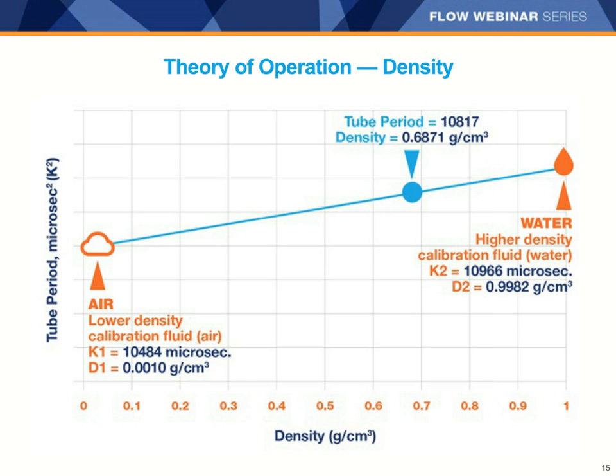The transmitter stores these values and automatically calculates the fluid density based on the tube period. In other words, if the tube period is 10,817 microseconds, the transmitter knows that the fluid density must be 0.6871 grams per cc to a very high degree of accuracy. Micro Motion meters can perform as good as plus or minus 0.0002 grams per cc. Micro Motion performs the density calibration in the factory. Field calibrations can also be performed using air, water, or virtually any other process fluid with a known density.